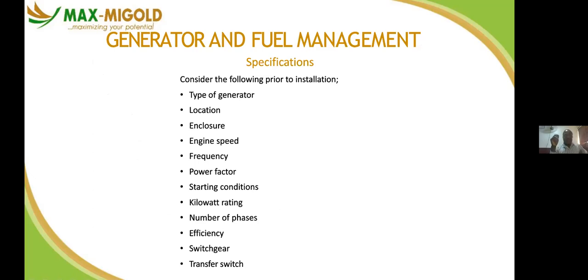So, generator and fuel management, we are still on generator and fuel specification. You consider the following prior to your installation. Before you install your generator, you consider the things that are listed here. The type of generator, is it single phase? Is it three phase? The location, the enclosure, engine speed. Our engine speed is 1,500. The frequency, we talked about frequency and so on. The acceptable power factor is 0.8. So you consider it, is it 0.8? The starting condition: how do I start it? Is it manually started or can it start electronically?